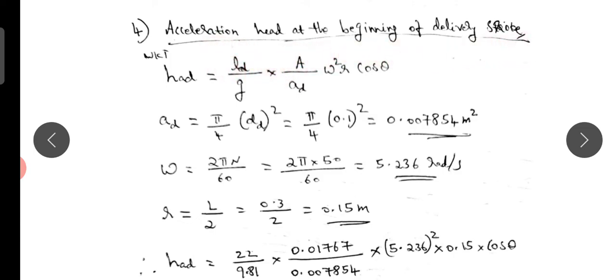Acceleration head at the beginning of the delivery stroke: the acceleration head in the delivery pipe is given by had = (LD / g) × (A / AD) × ω² × R × cos θ. Here, capital A is the cylinder area and small AD is the delivery pipe area. The area of the delivery pipe, AD = (π/4) × DD² = 0.007854 m².